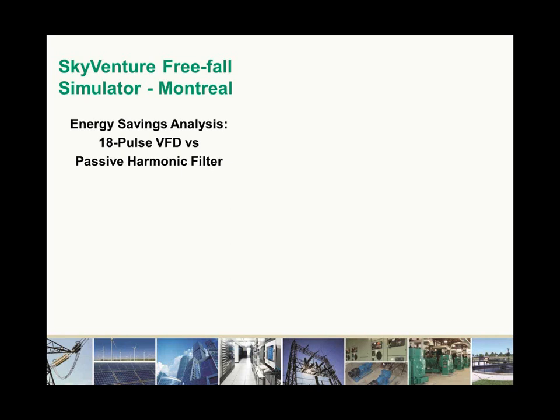An 18-pulse solution was also considered, and although it could meet the requirements of IEEE standard 519, provided the applied voltage is fairly balanced, because if you have unbalanced voltages, multi-pulse systems do not perform very well. But if the voltage was reasonably balanced, it could meet IEEE 519 compliance. The simulation software was also used to compare the 18-pulse option with the Lineator AUHF option to show that significant energy savings could be realized with the Lineator solution.